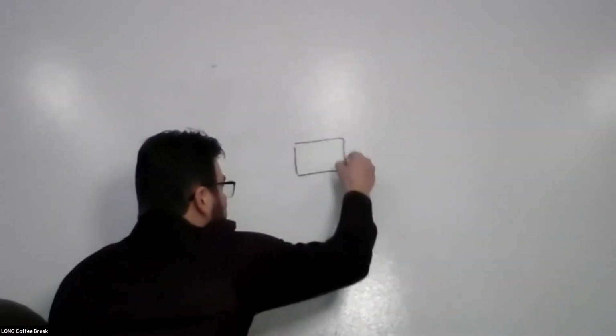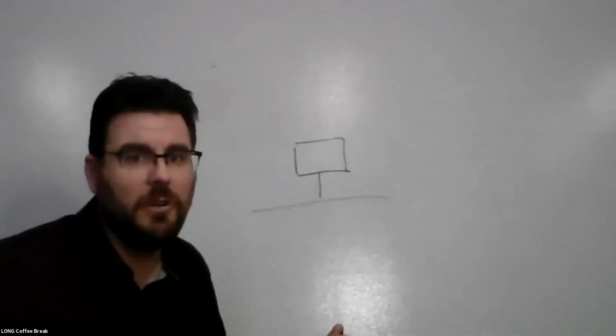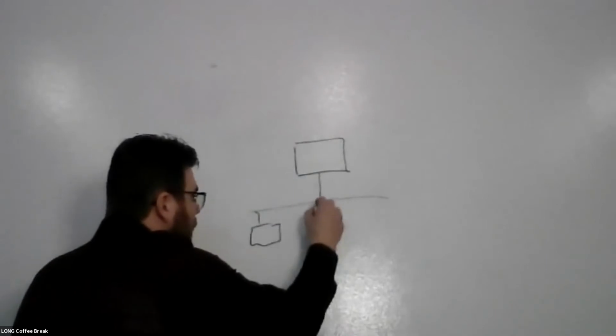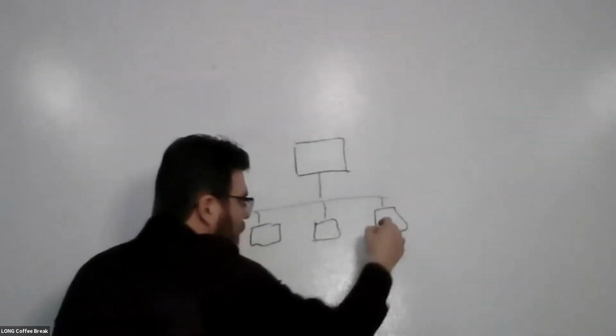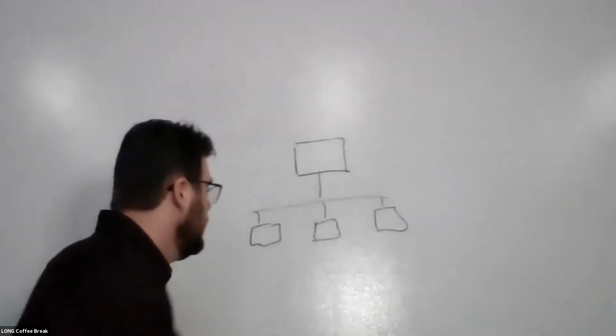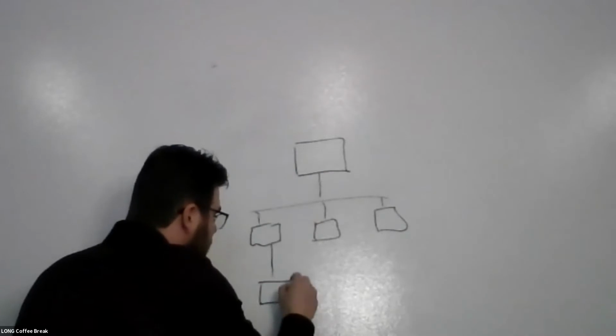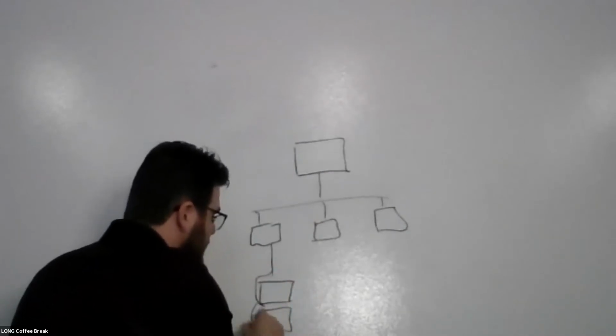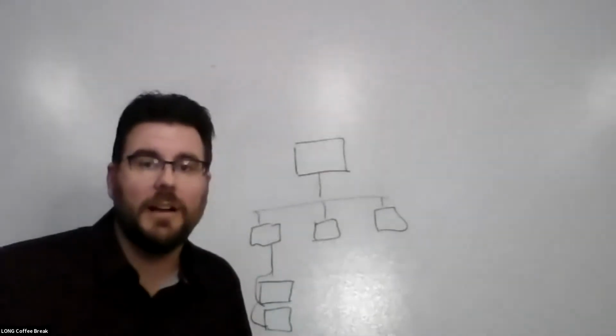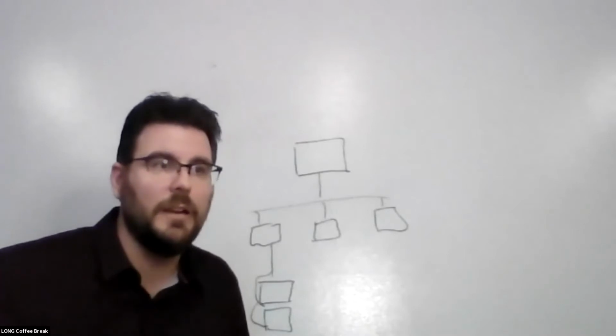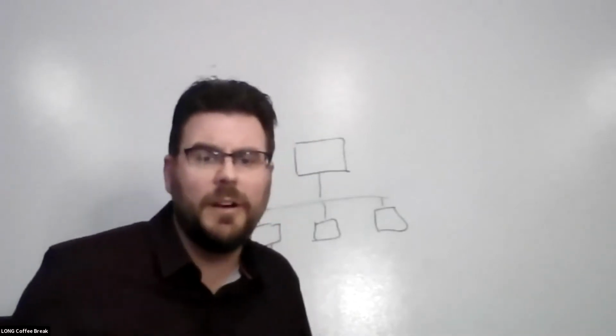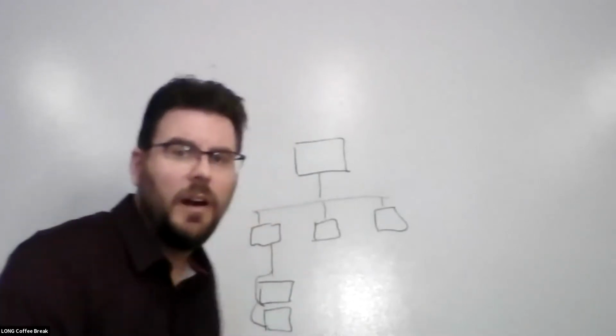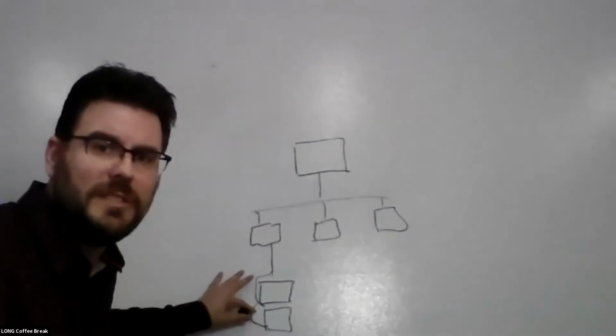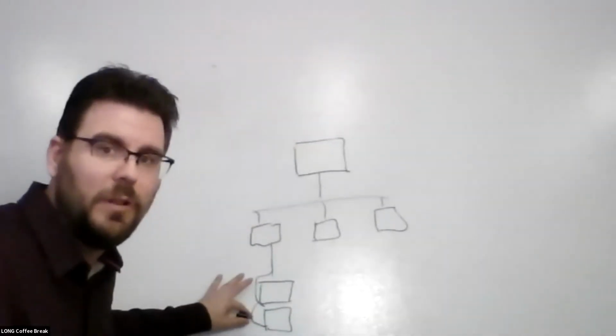So typically on a control system, you've got three levels. You have some server at the top. Below that, you've got some sort of network where you have a controller operating a piece of equipment: an air handling unit, a chiller, a boiler. And below that, you've typically got a field level network where you've got VAV boxes, fan powered boxes, heat recovery, heat pumps, or even chill beams. You've got other smaller controllers down at a floor level network.